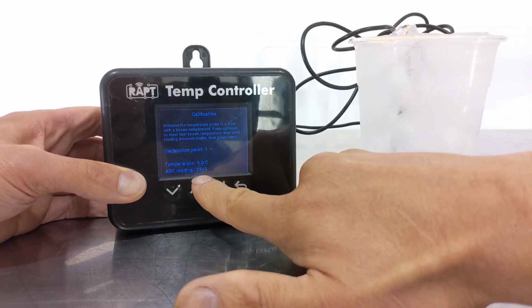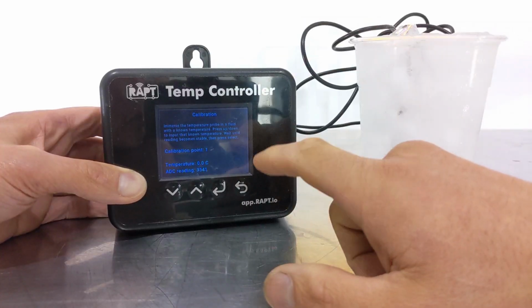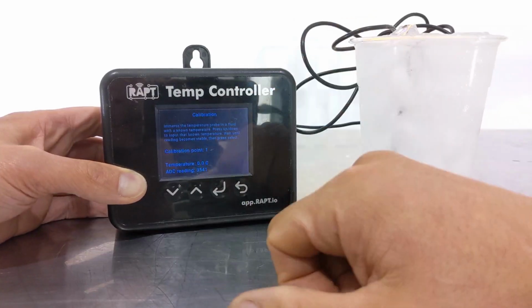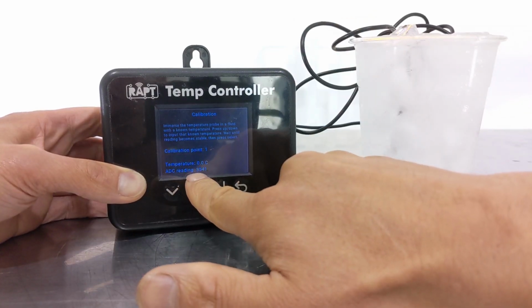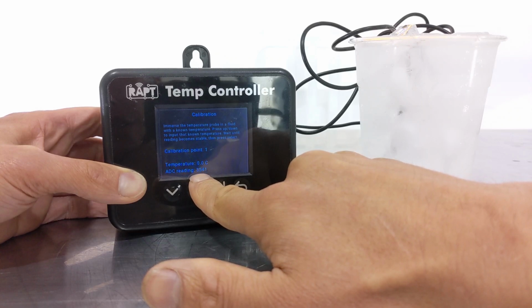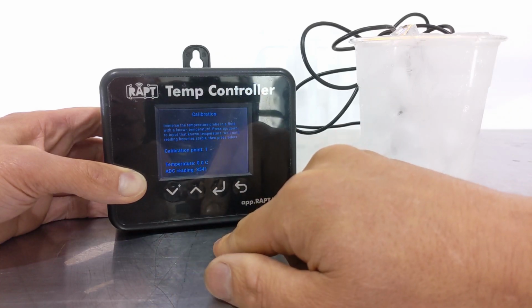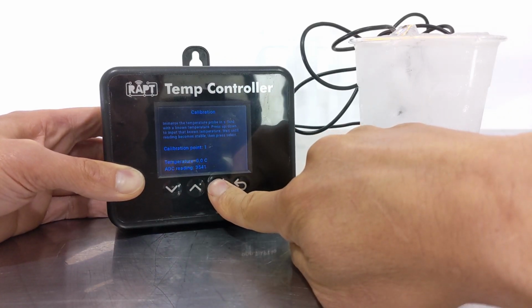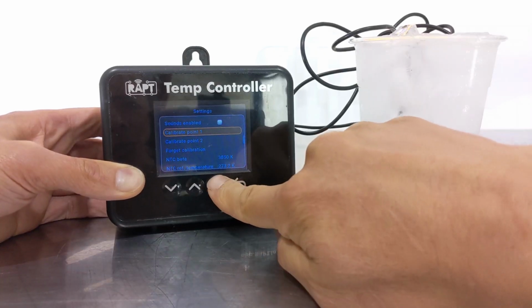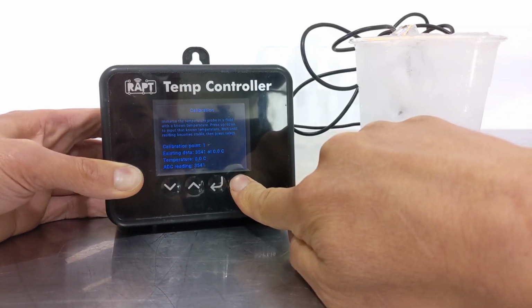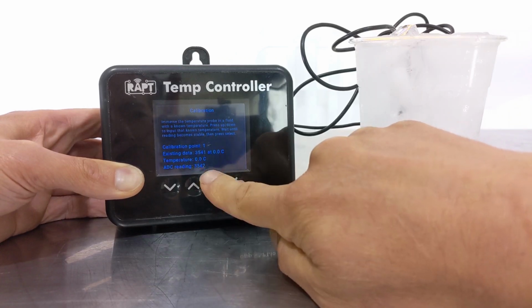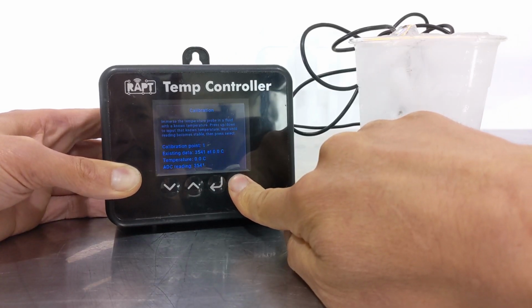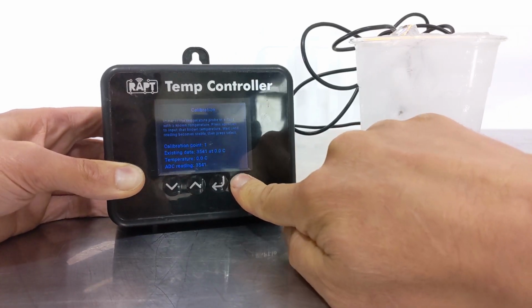Or if you make an extension to the probe, some people are extending the wire, you might want to do this process again. But you can see how very much stable it is. It's at 3541, barely changing at all. So I can hit enter, and that'll save that calibration probe reading there. And as you can see, it's already got that reading saved at calibration point 1.